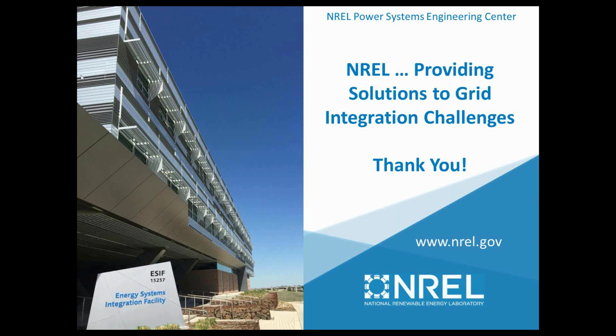Maybe this is something that we take offline and try to do a little bit more in-depth study on, because one of the big challenges is that there are potentially solutions for overvoltages and for this unintentional islanding that require very expensive solutions. So coming up with some lower cost solutions for addressing some of these issues would probably be critical to take a look at. But we could probably reduce that to a subset here, taking a look at these overvoltages on the single line to ground fault and what to do about direct transfer trip costs.